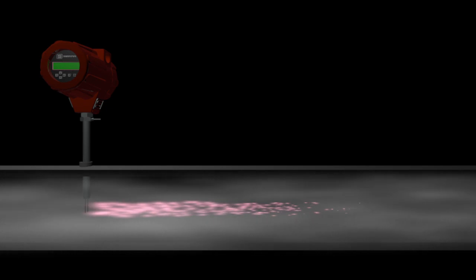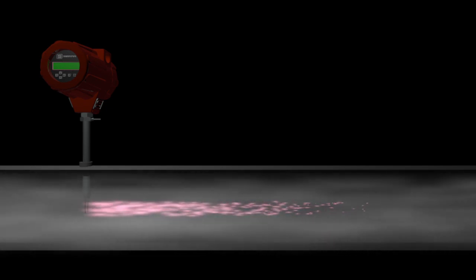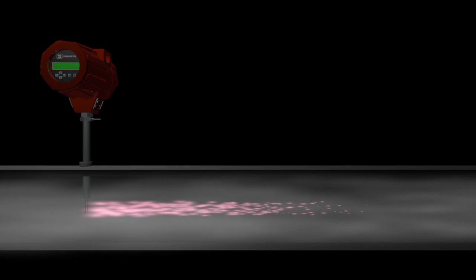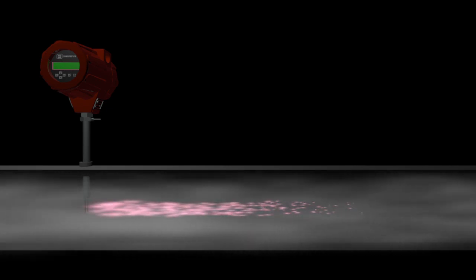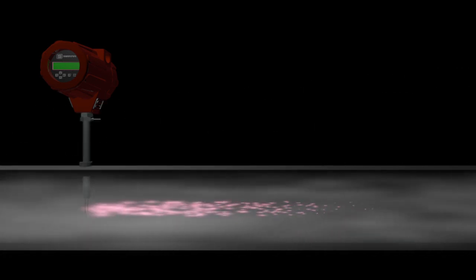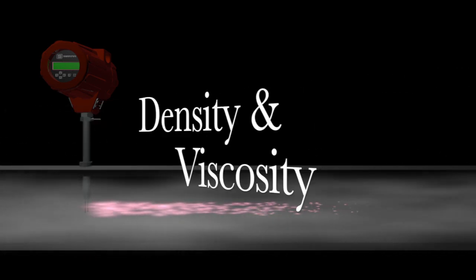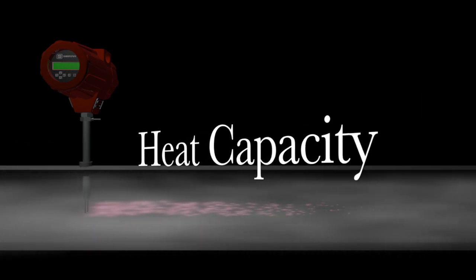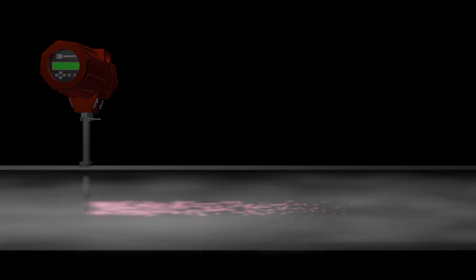It is important to note that heat transfer from flowing gas is affected by the properties of the gas. These are known gas properties like thermal conductivity, density and viscosity, and heat capacity. All of these must be understood and accounted for when a thermal meter is calibrated to assure best accuracy.